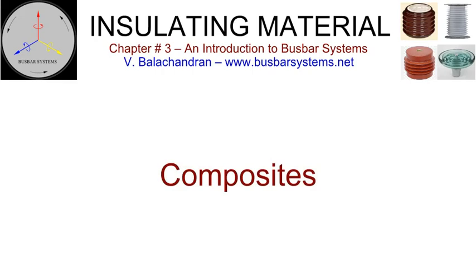A composite insulator comprises a glass-reinforced core, covered with a silicone rubber casing. The glass-reinforced core provides the necessary insulation and mechanical strength, while the covering protects against ultraviolet radiations and atmospheric pollutants. The covering can be profiled for desired creepage distance.